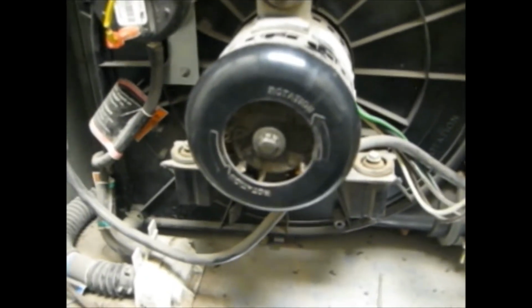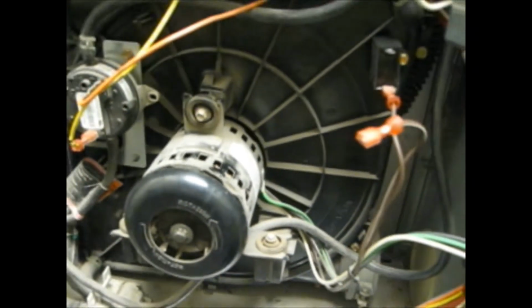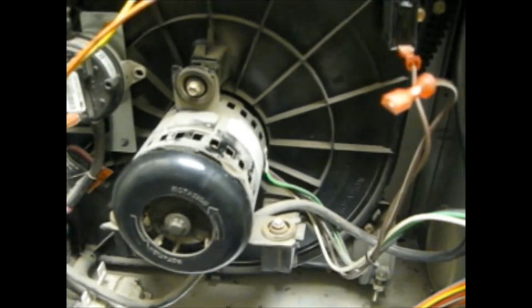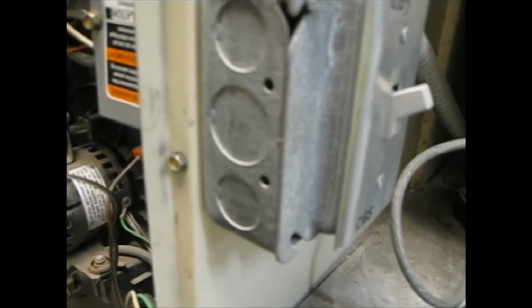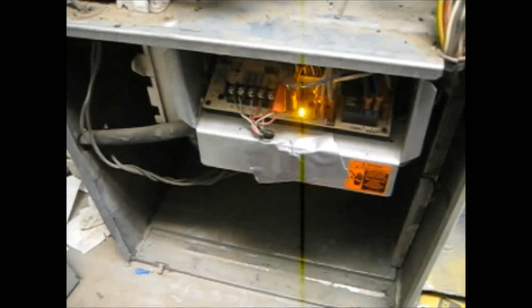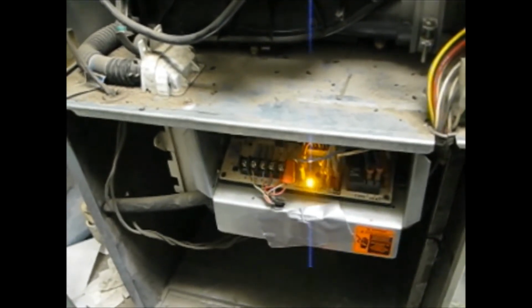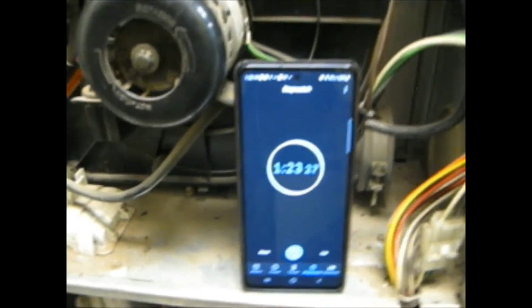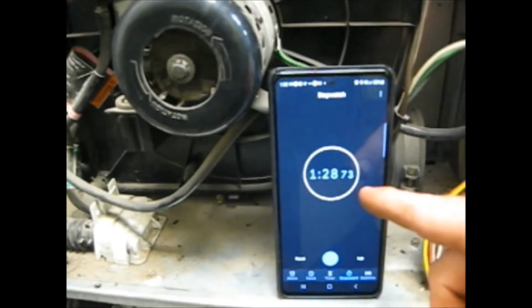Capacitors are easy to test if you have the right equipment. I'm going to simulate what happens when a capacitor goes bad. I'm going to do this by removing the contact from the capacitor and then starting the furnace to see what happens. We're going to go ahead and turn on the furnace, and we're going to have to wait the 90 seconds for the system to purge itself. We're approaching 90 seconds, and at 90 seconds the fan below should turn off and the inducer motor should turn on.